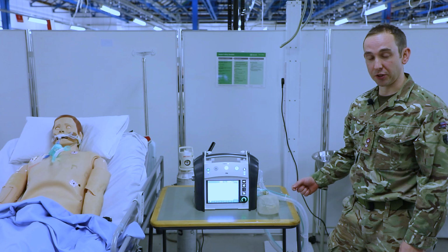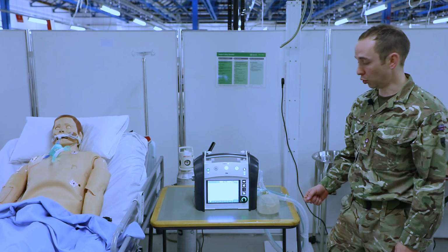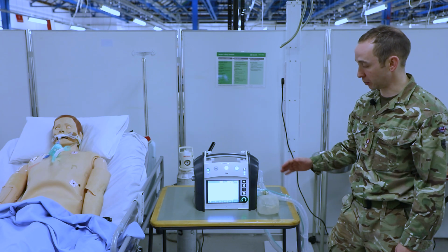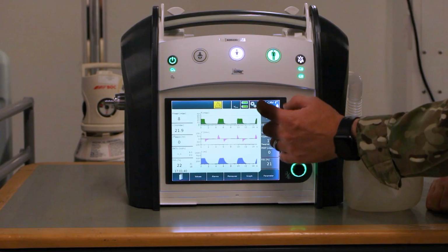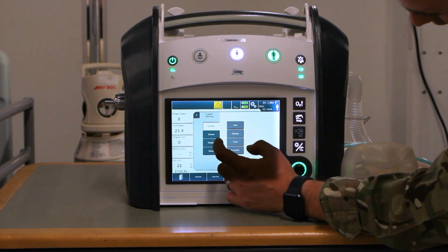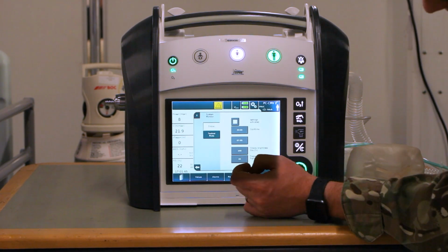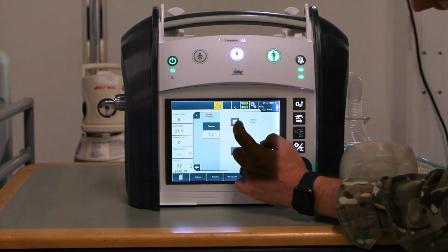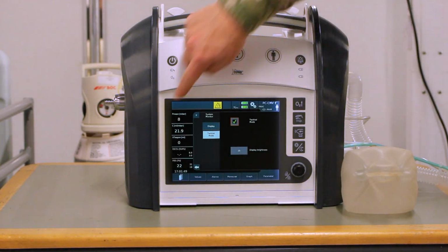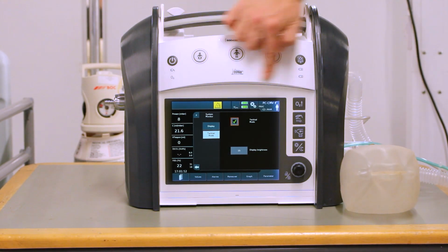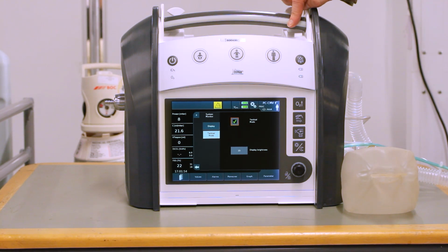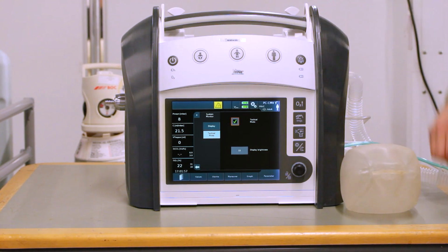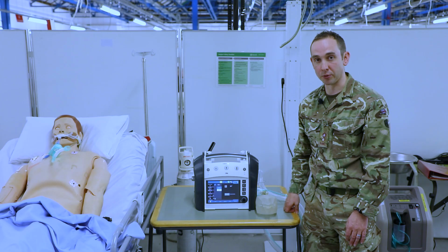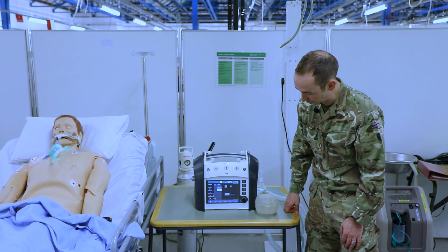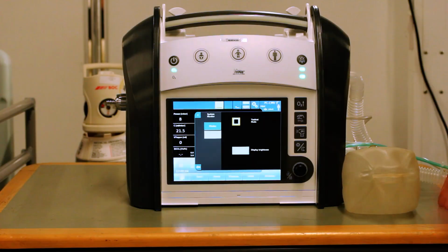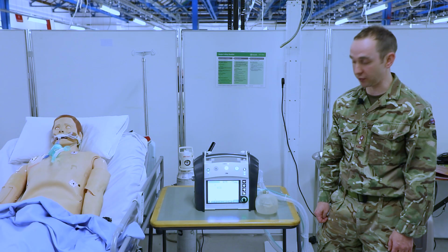It is possible to set this up in tactical mode, which will turn off all visual and auditory alarms and dim the screens completely. To do this, go into Settings, then System, Display, Tactical Mode, tick Tactical Mode, and you will see that the screen goes darker. It has turned off all visual alarms, but also it's turned off all auditory alarms. Ensure that you do this knowing that those alarms are now disabled. If you want to convert back, just untick the box, and that will re-engage all the previous alarms that have been set.